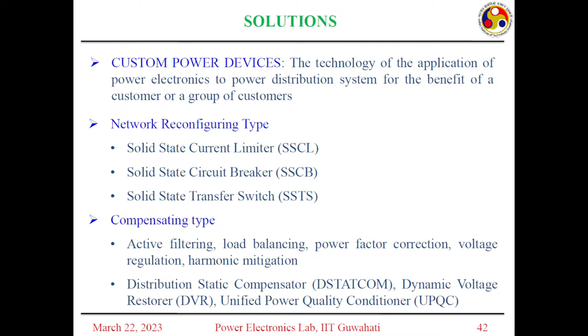Okay, so let us see an introduction to these solutions. Now the DSTATCOM, distribution static compensator, is used in the distribution system. The STATCOM is used in the transmission system, the DSTATCOM is used in the distribution system. DSTATCOM has more control flexibility and more functionality compared to a STATCOM. STATCOM generally is used for reactive power compensation, and in transmission systems generally we don't do harmonic compensation. In transmission systems, the major problem is reactive power, so STATCOM generally caters to reactive power issues.